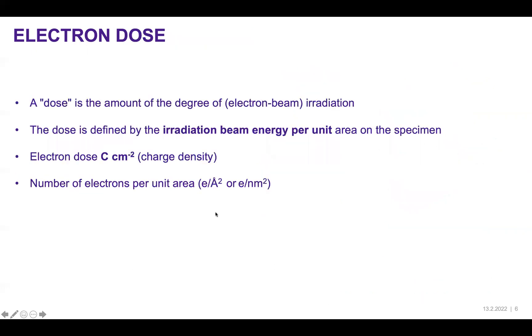When we talk about electron dose, a dose is nothing but the degree of electron beam irradiation. The dose is generally defined by the irradiation beam energy per unit area on the specimen, typically expressed in coulombs per square centimeter. We can control electron dose by controlling the number of electrons per unit area, usually represented as electrons per square angstrom or per square nanometer.